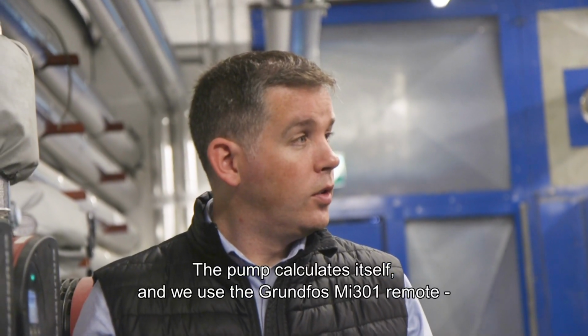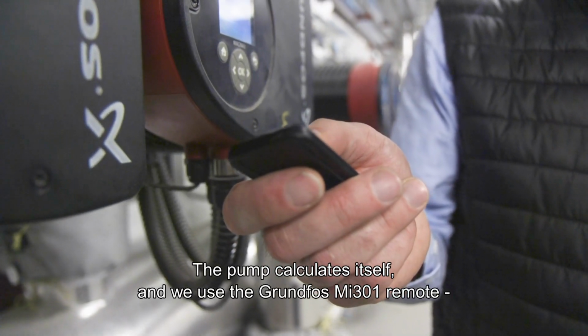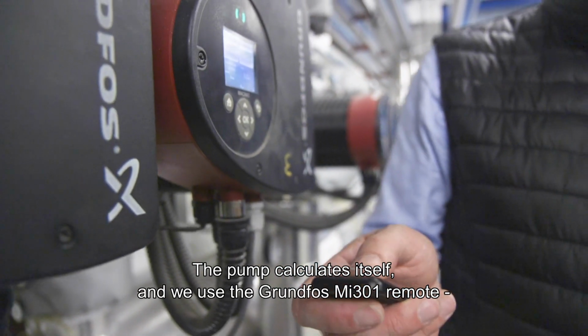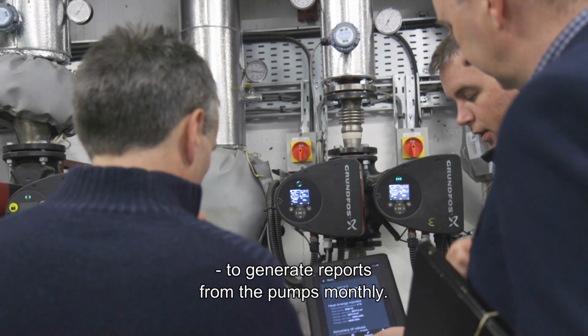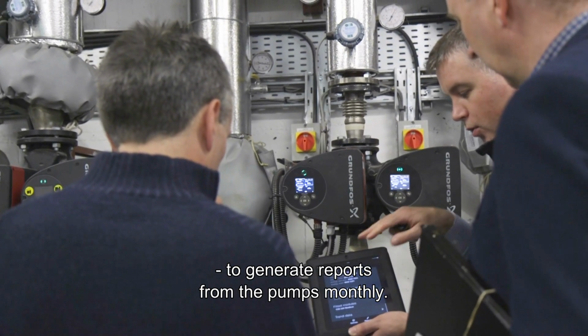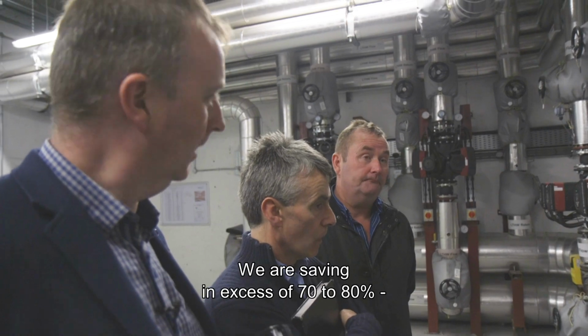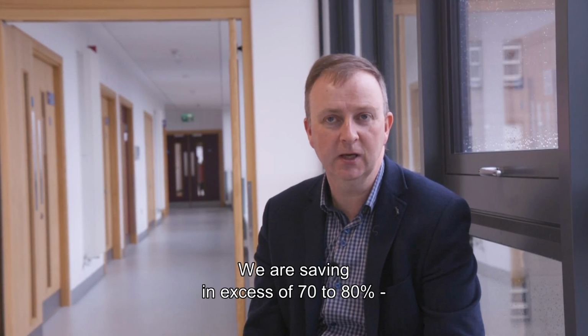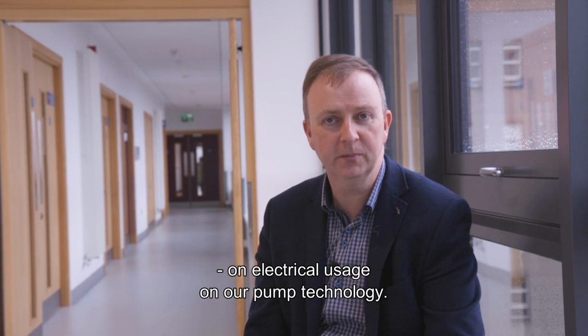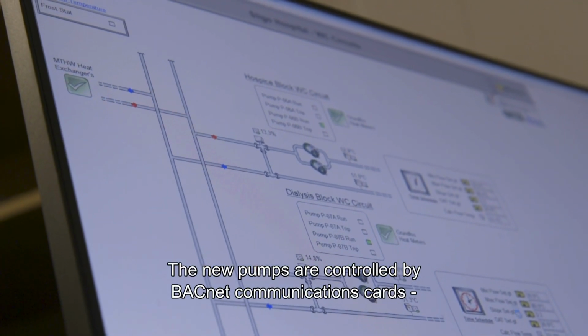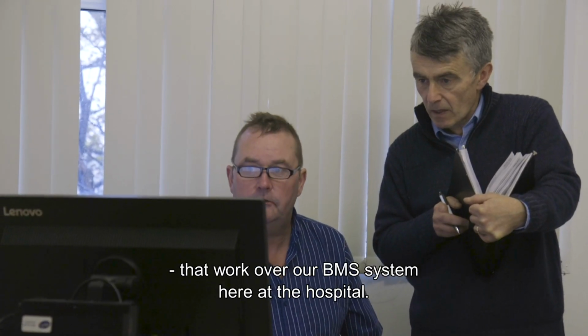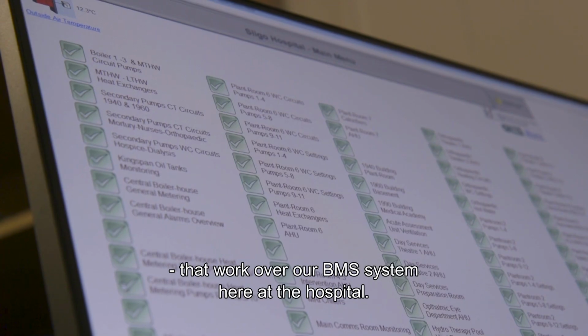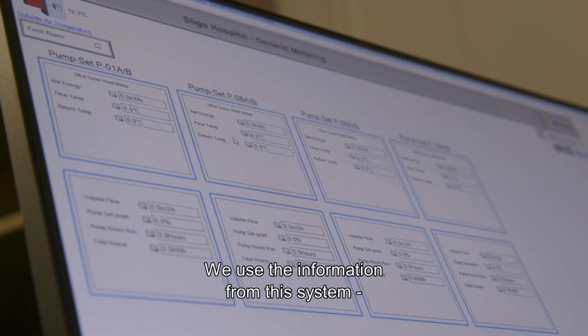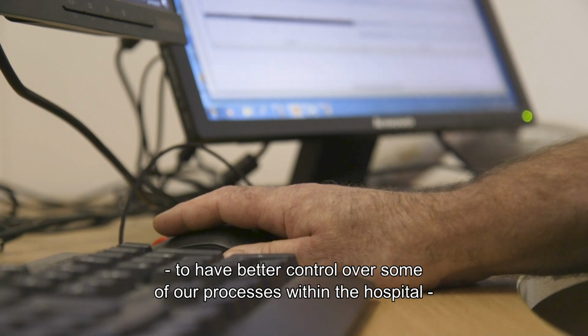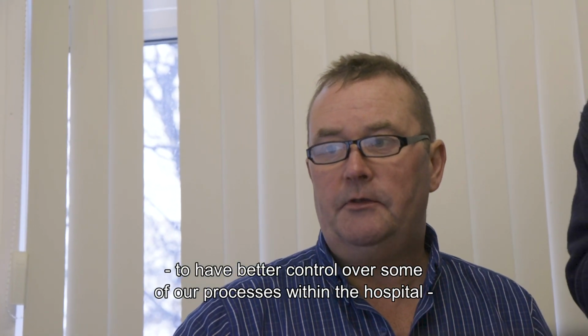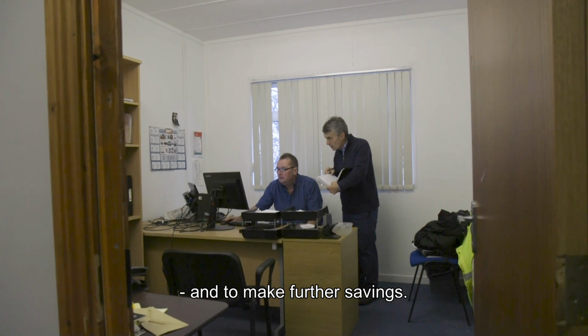The pump calculates itself, and we use the Grundfos MI301 remote to generate reports from the pumps monthly. We are saving in excess of 70 to 80% on electrical usage on our pump technology. The new pumps are controlled by BACnet communications cards that work over our BMS system here at the hospital. We use the information from this system to have better control over some of our processes within the hospital and to make further savings.